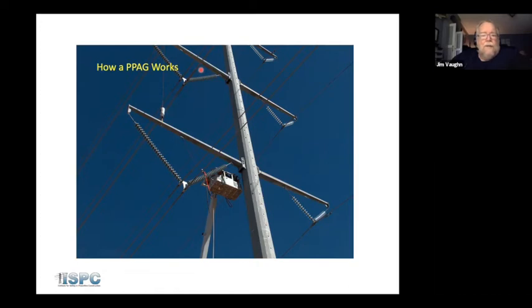Now, back in the 70s and early 80s, when I was a transmission lineman, we were using air gaps. They only protect the worker. They raise the possibility of an inadvertent lockout somewhat, and that makes utilities afraid of them. But utilities have to understand their responsibility in controlling these TOVs and protecting the worker out on the line, and a lot of them don't do a very good job at that. Now, this is how a TOV works, or how an air gap or a PPAG works. We don't put the PPAG on the pole that we're working on, but I'm going to show you a graphic here to show you how it works.